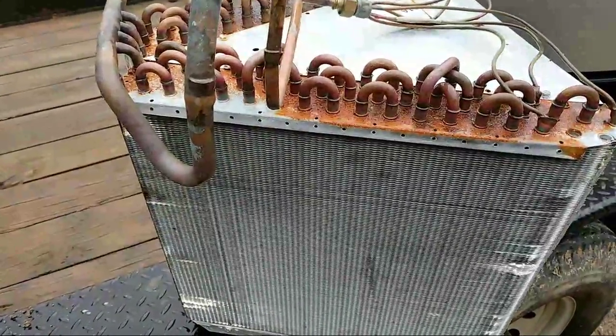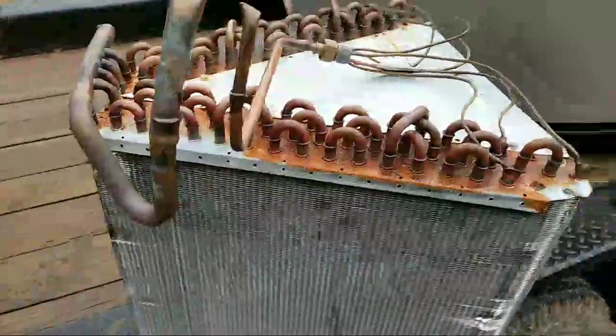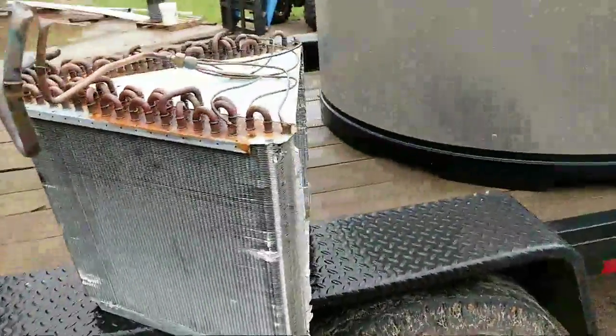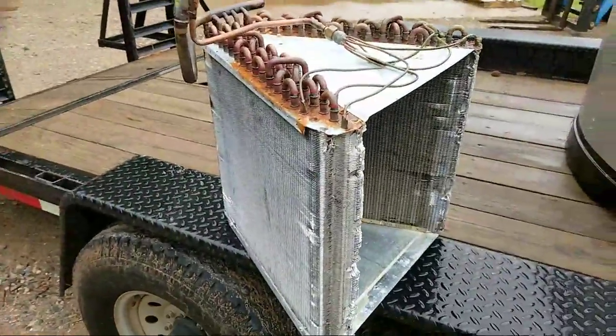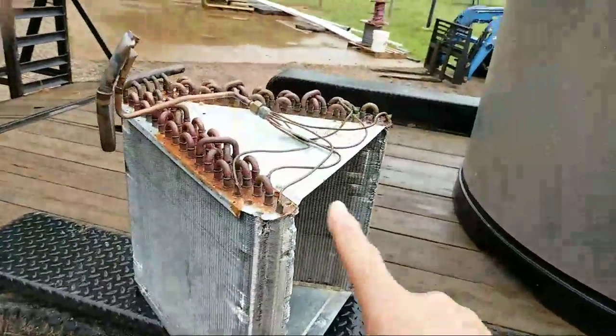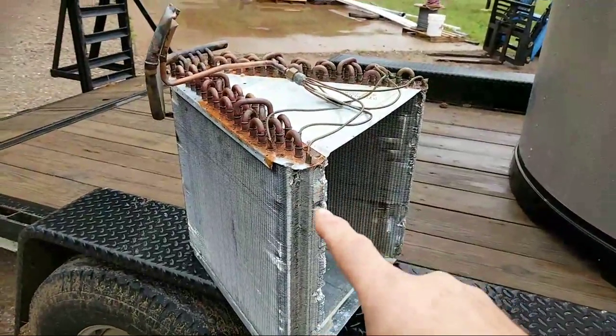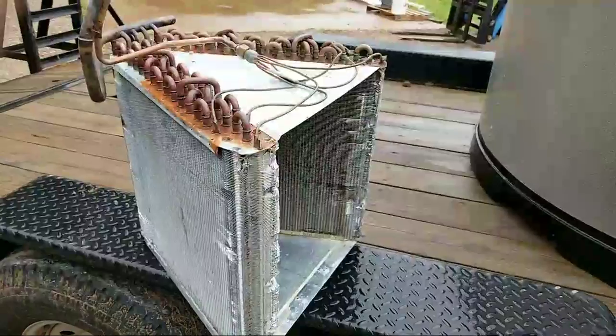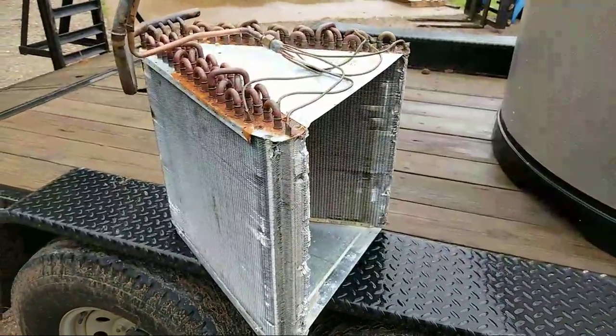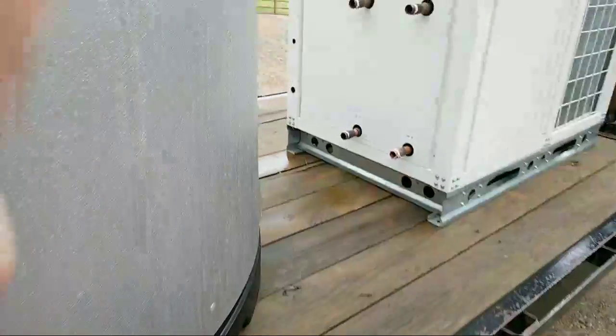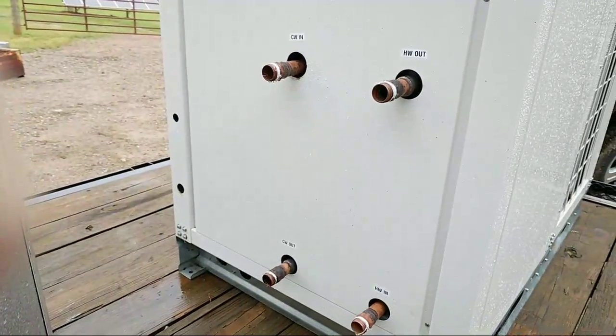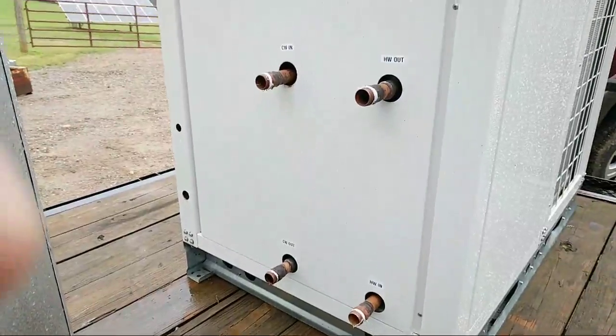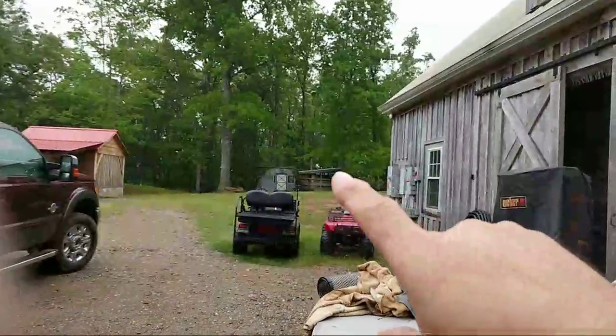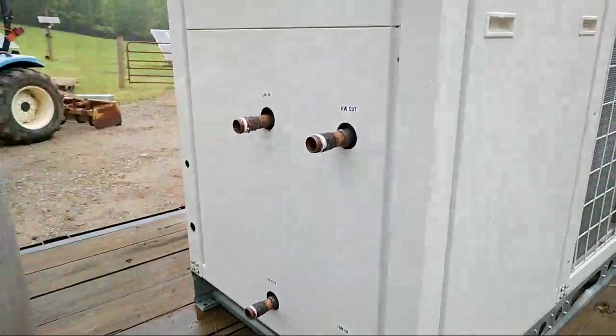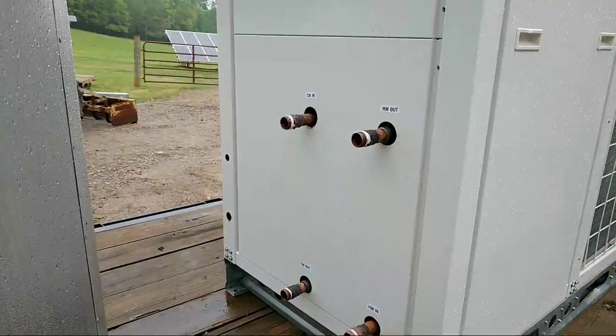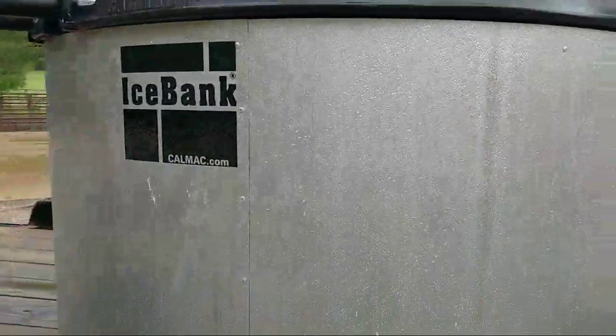Is your setup just replacing the evaporator coil with a chilled water coil? No, my setup is replacing everything to do with refrigerant. I pulled out the line sets, I ripped out the coils. So I have 2 coils in my air handler: this hydronic A coil for air conditioning, and another coil radiator cut in for the heat side, the hot side. So I can feed both coils with the cold and hot water, or the hot water from my wood boiler, which is over there. I can switch seasonally if I want to. I don't need ice in the winter, I turn this tank into a hot water tank if I want to.